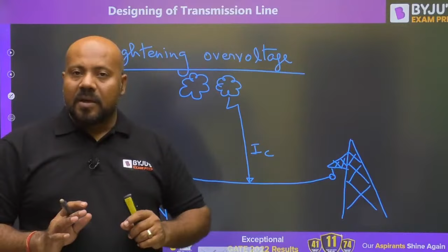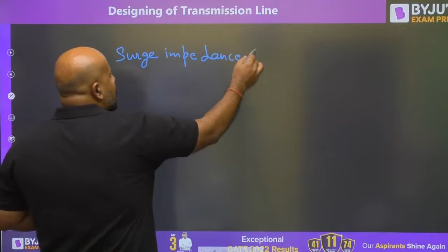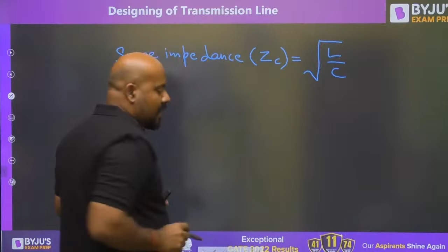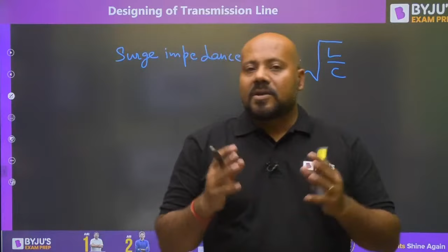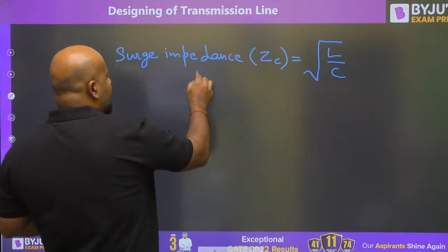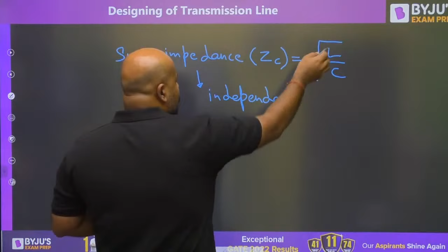The behavior of the transmission line is always going to be with respect to the surge impedance. When we talk about surge impedance in detail later, understand that we define it as root of L upon C, where L is the series inductance of the transmission line and C is the shunt capacitance of the transmission line. This surge impedance is independent of the length of the transmission line, because there is no length term.